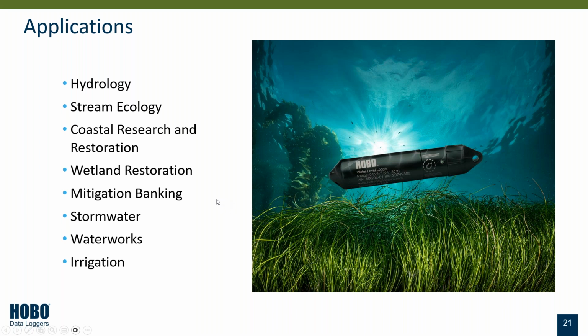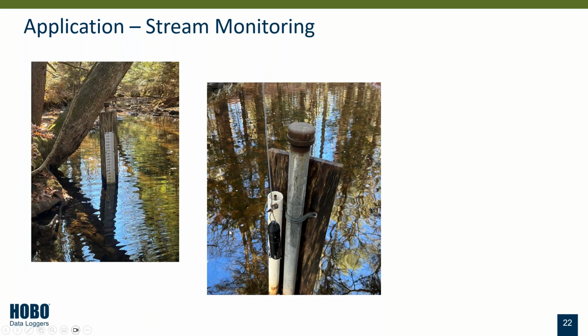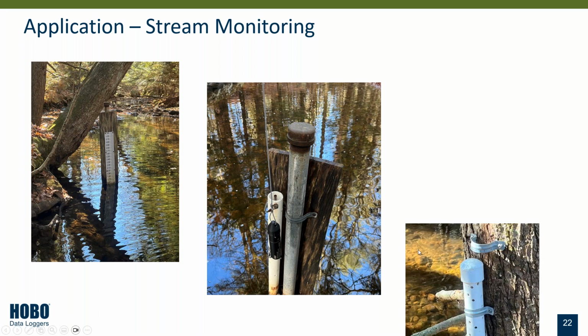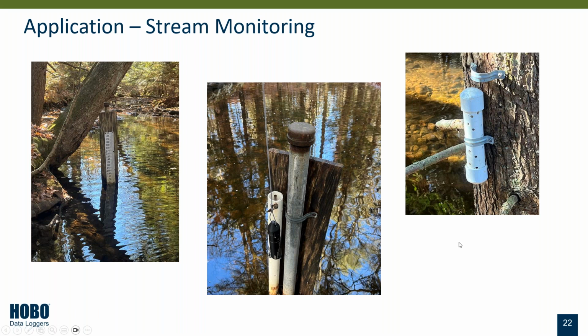So I'm looking at time. I'm going to go through the applications pretty quick, in the spirit of time. I'm sure you all have your own applications, so I think you have a good idea of what you're planning to do. You can see many different ways that water level data is used. Probably no surprise there. Here's an example of a stream monitoring application, probably one of the most common ways that our water level loggers are used. So here's a staff gauge, and this is the backside of that staff gauge. You can see they have a 1.5-inch PVC well with the water level logger installed. And of course, there's a barometric pressure logger on a tree next to the stream. So you want to have that data as well.